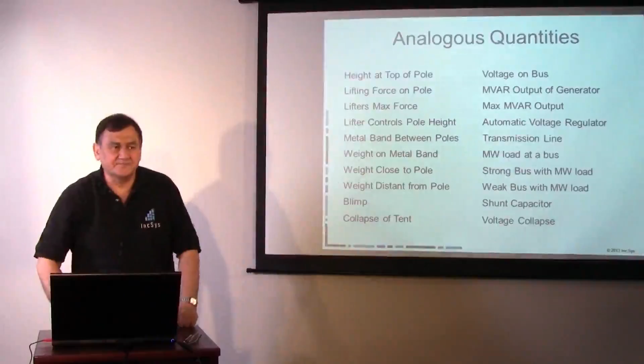But when we have a radial transmission line, you don't have voltage control at that end, so it's like a lifter at one end with the beam sagging significantly. So wherever you can, make sure you've got good support throughout your system, and you have to make sure that those generators keep their units on in automatic AVR mode. And time and again, you'll see in the standards, if a unit is coming off, they have to tell the system operator, because that can have a dramatic impact on voltage stability.